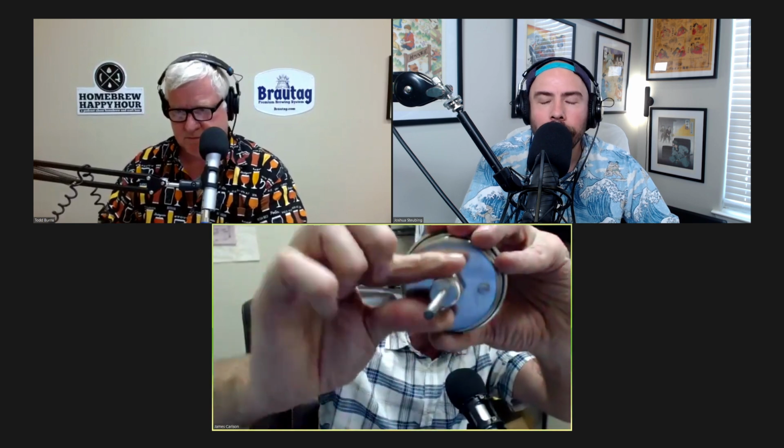So you can either put it in boiling water and adjust it to 212, or you can put ice in a cup, a lot of ice in a little water, and really shake it hard and adjust to 32. Either way. Okay. Just pack the cup full of ice, as much ice as you can get in it. Top it off with water, and then you want to turn this little screw right here, this little head, till it'll adjust the temperature to 32. Interesting. And that's how you calibrate a dial thermometer. And if it doesn't have this, then you can actually take the body and the nut, and you can adjust it that way. A lot of times the nut is that, right? So yeah. Interesting. Cool.